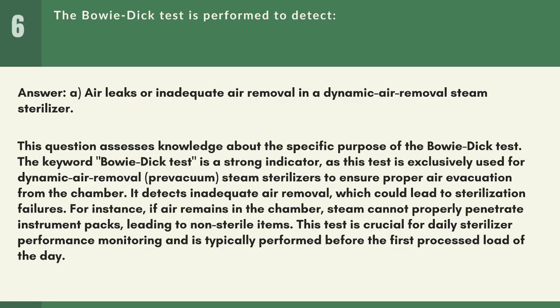This question assesses knowledge about the specific purpose of the Bowie-Dick test. The keyword Bowie-Dick test is a strong indicator, as this test is exclusively used for dynamic air removal, pre-vacuum, steam sterilizers to ensure proper air evacuation from the chamber.